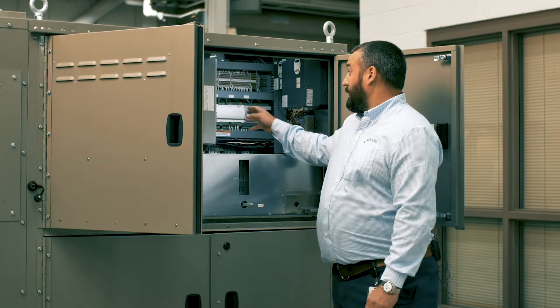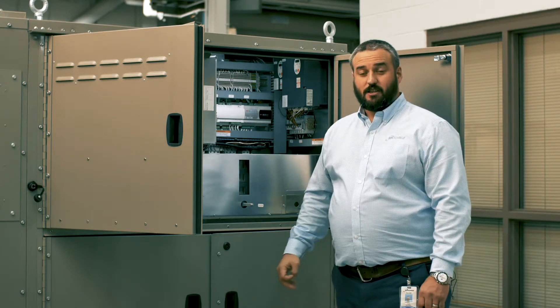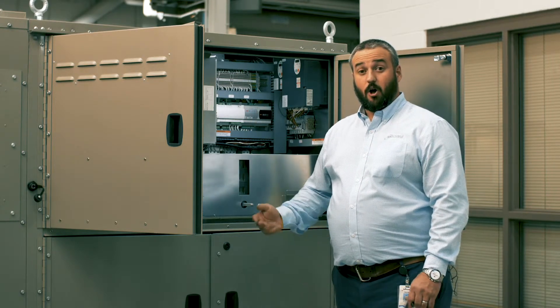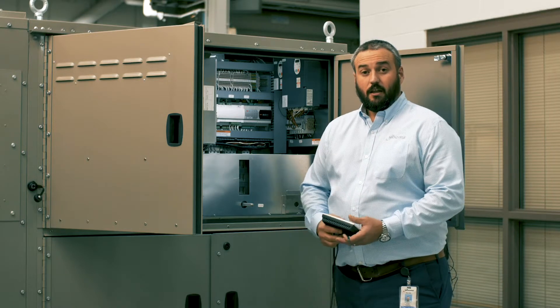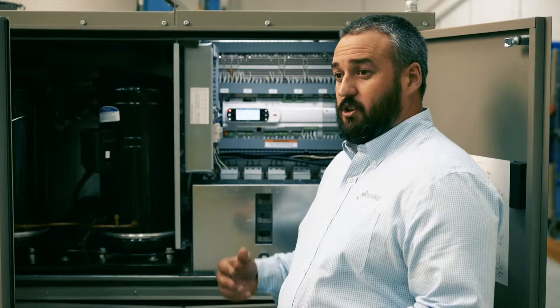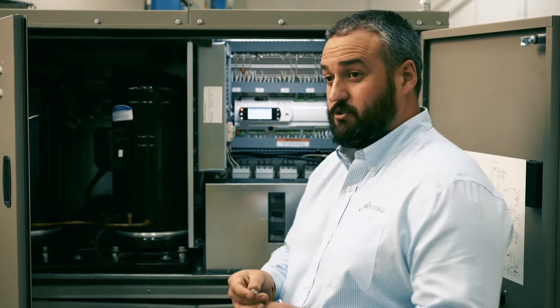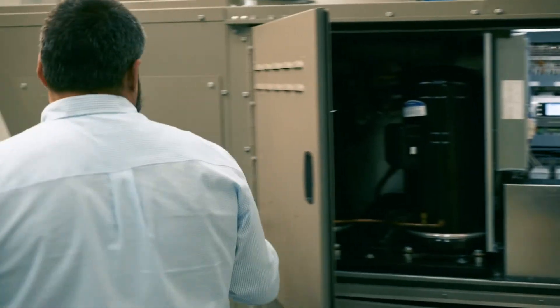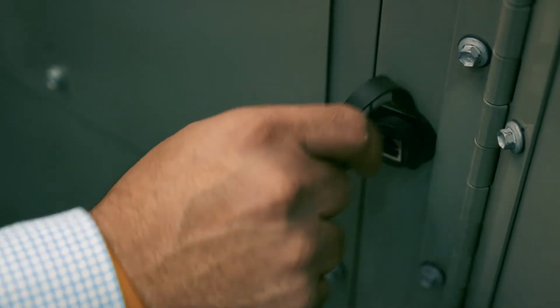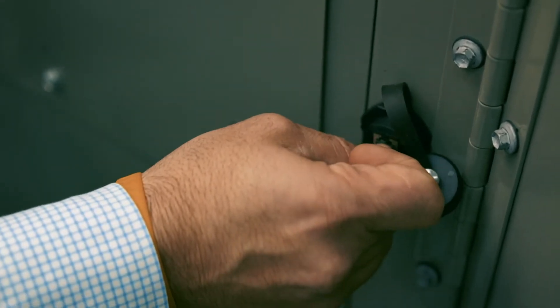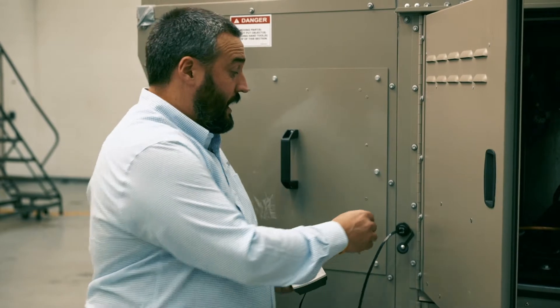Because the controller is mounted in a high voltage panel we've added the option for a remote port to plug in your display. The reason we've done this is because the unit would have to be switched off by the isolator to plug into the controller so this is really nice for a service engineer because they have the option to connect into the unit and read all the values without having to shut the unit down.